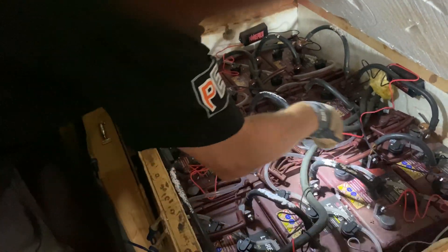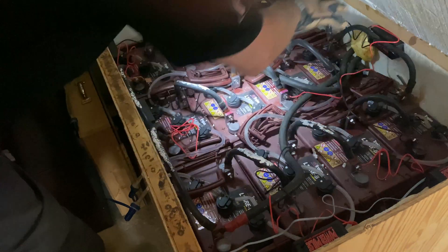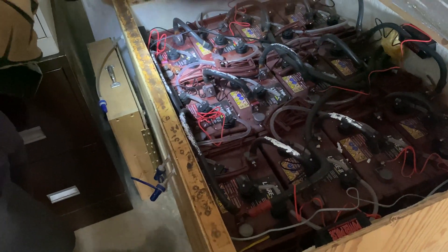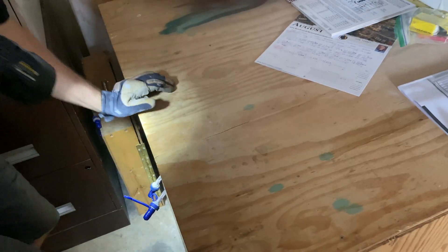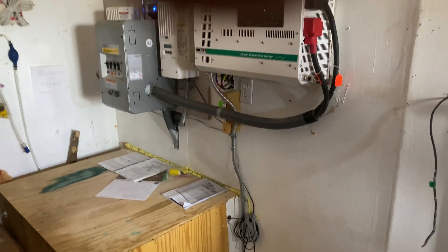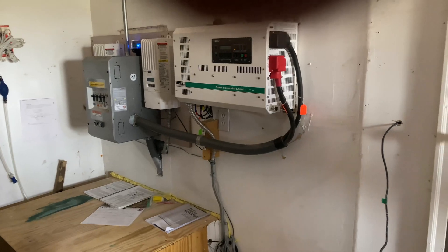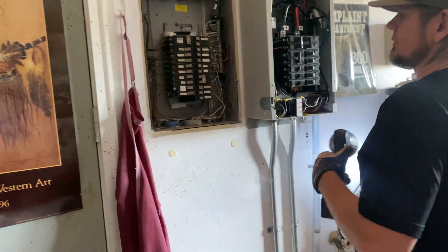He's able to pump water by feeding these in series and they all stay filled with distilled water — distilled when you buy it, not boiled. You can see how that windmill was finally cut off. There's no fusible disconnect out there; it should have had a fuse and it wasn't grounded properly.